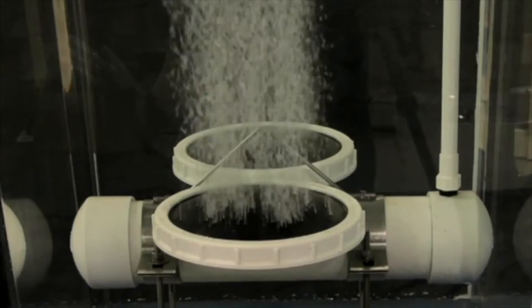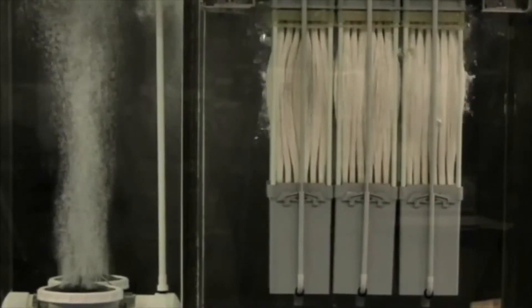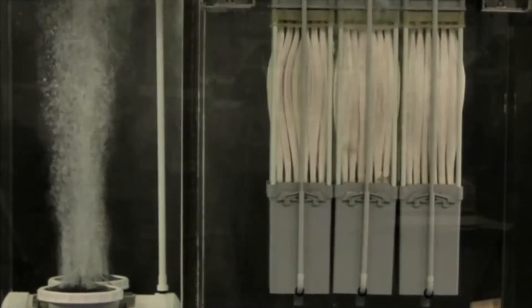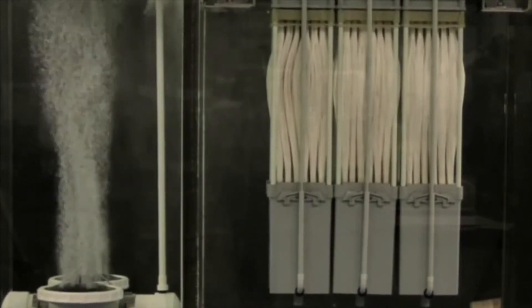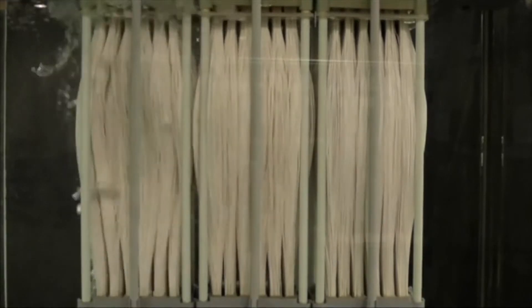In fact, when compared with air scour in conventional MBR systems, MemPulse uses roughly half the aeration energy for the same membrane performance. This is because small bubbles can't provide as much energy to shear off solids and agitate membranes.